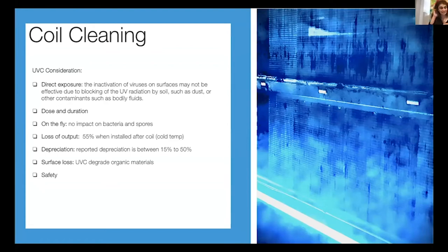Depreciation, I think, is very well understood, because the light intensity will basically diminish with time. Surface loss: it's not plug and play. If you are retrofitting your air handling unit with UV light today, it's not plug and play because you have to shield any organic material. For example, if you put it before the coil, after the filters, it's going to ruin your filters, etc. And then the last one is safety. Make sure, because it's going to be a maintenance nightmare, of safety for the skin and for the eyes.